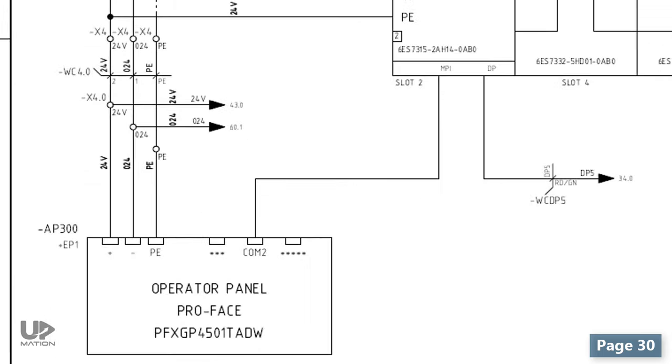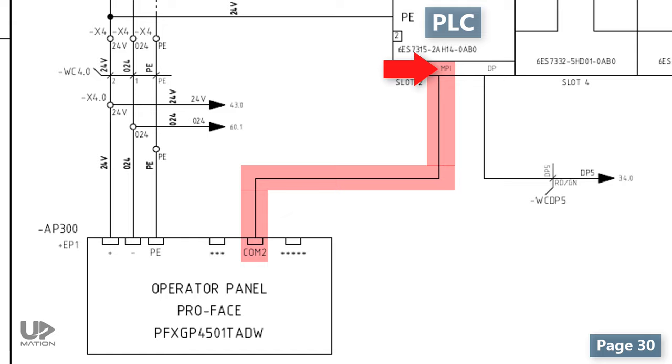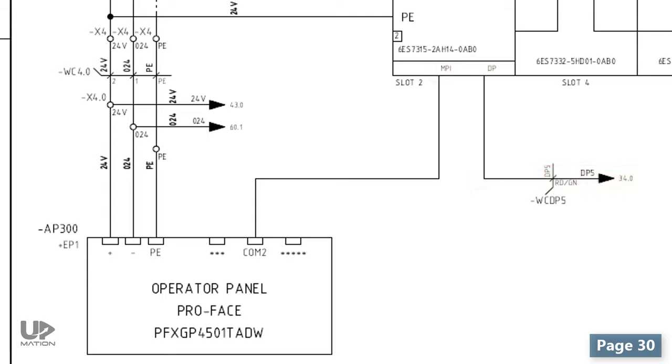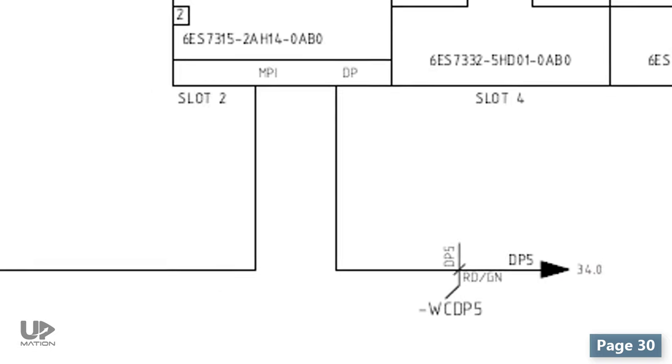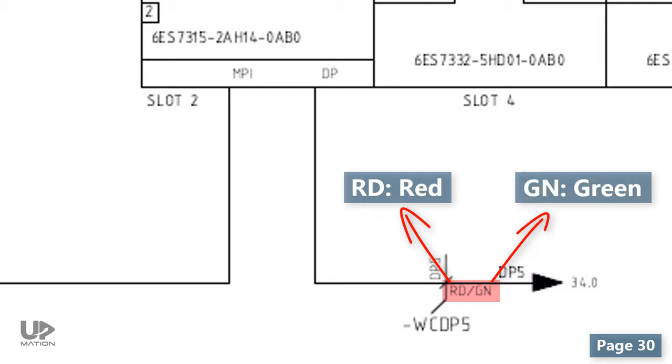You also see communication cabling here. The operator panel is communicating to the PLC directly via the MPI port of the CPU using a PROFIBUS cable. The WCDP5 cable is also a PROFIBUS cable as it's connected to the DP port of the CPU. And this is the color of the cable, which is red with green strips.